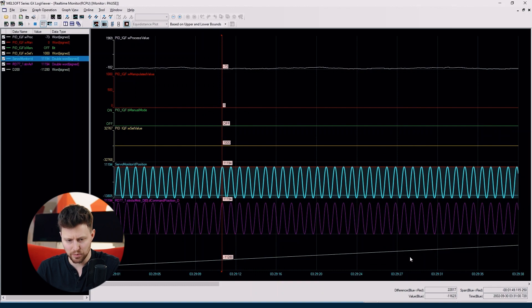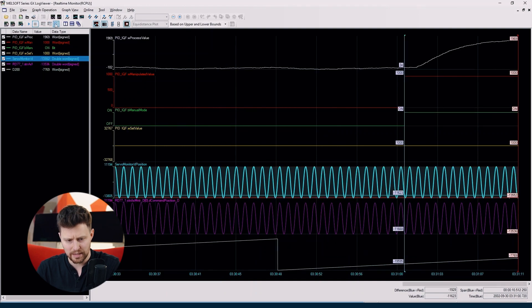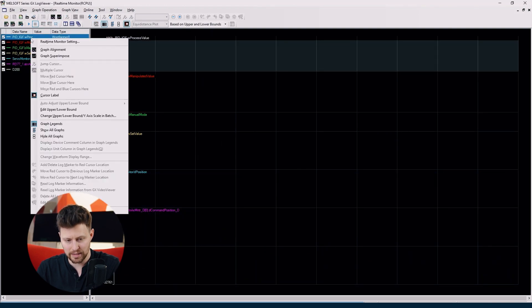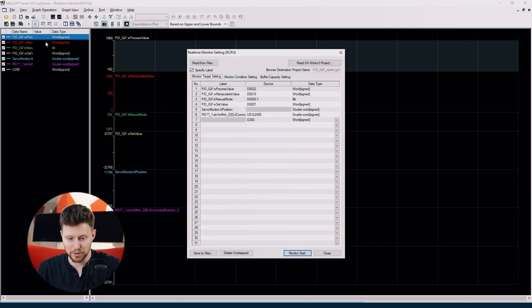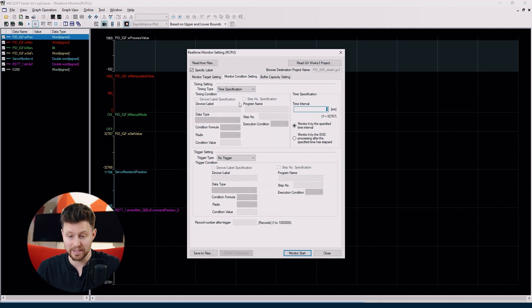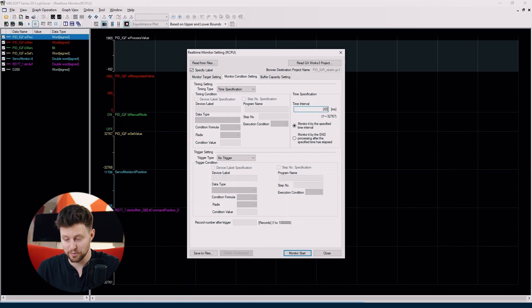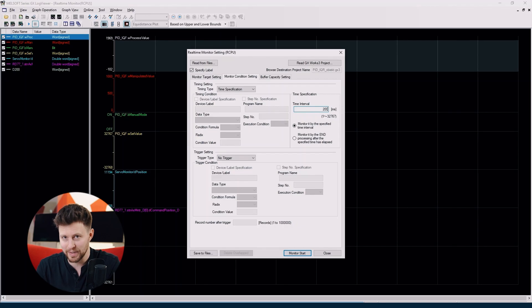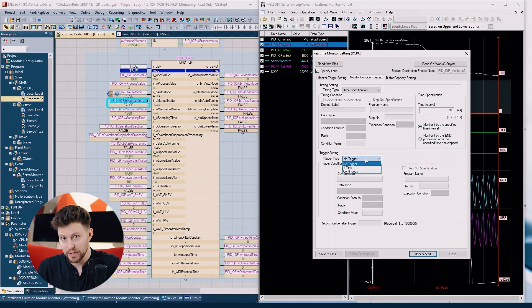The next function I want to show you requires clearing the graph first. Right-click on a signal and go to the real-time monitor settings. Here we can go to monitor condition setting where we can, first of all, change the sampling time — so we don't have to use the sampling time of each PLC scan. It can be, for example, 200 milliseconds, which is enough for my PID. We can also use triggers — some of our registers can act as triggers.